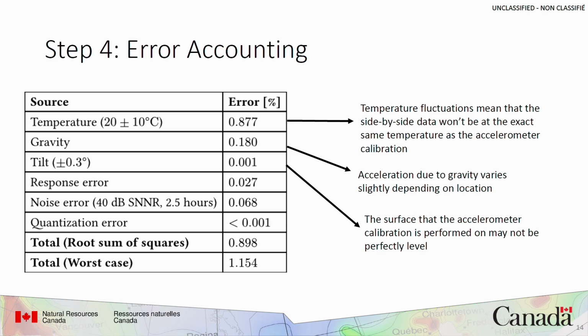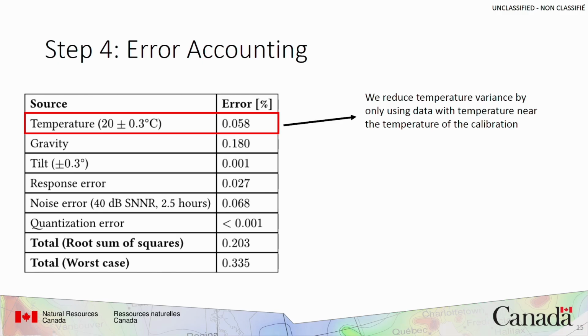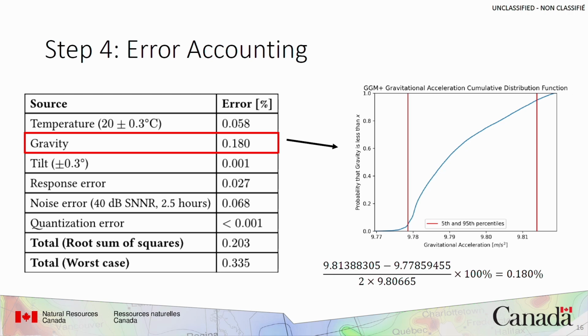So here's what our error budget looks like if we don't account for temperature and don't account for local gravity, just use the standard value for G. The total RMS error is almost 1%. So we do, advance please. If we first account for temperature, we're doing much better. The total RMS error is 0.2%. And advance, please. If we then account for the local value of gravity, the total RMS error is approximately 0.2%, which is looking pretty good.